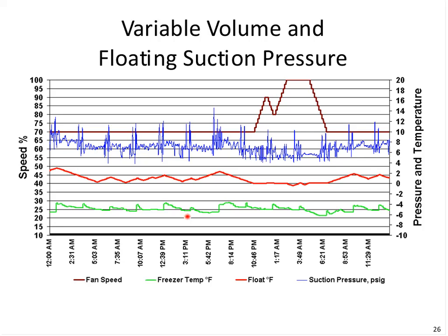Notice temperature went below the set point. Float started occurring again. And then we're above the set point. So the float comes down, then no float. And we're still above the temperature, say right here, with zero float, so then we start speeding the fan up. Notice we regained temperature a bit, but then lost it again above the set point. No float, fan went up to 100% speed.